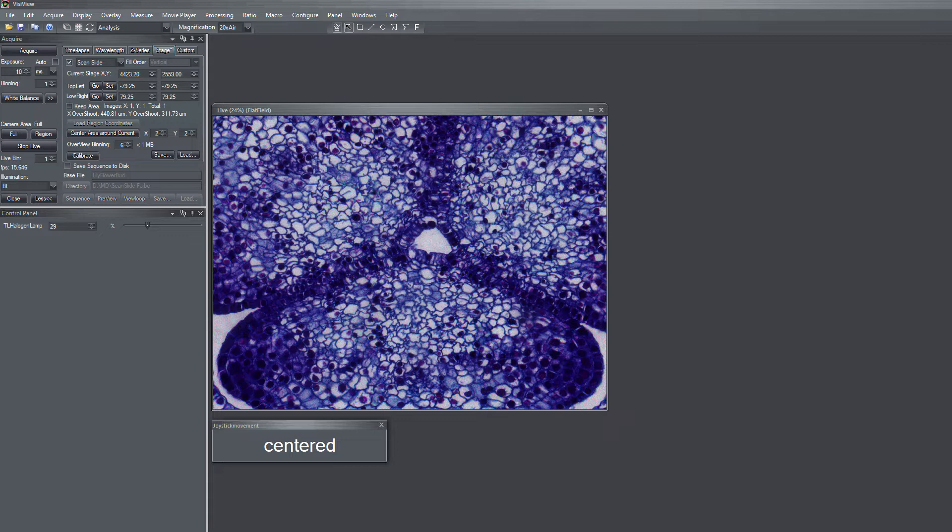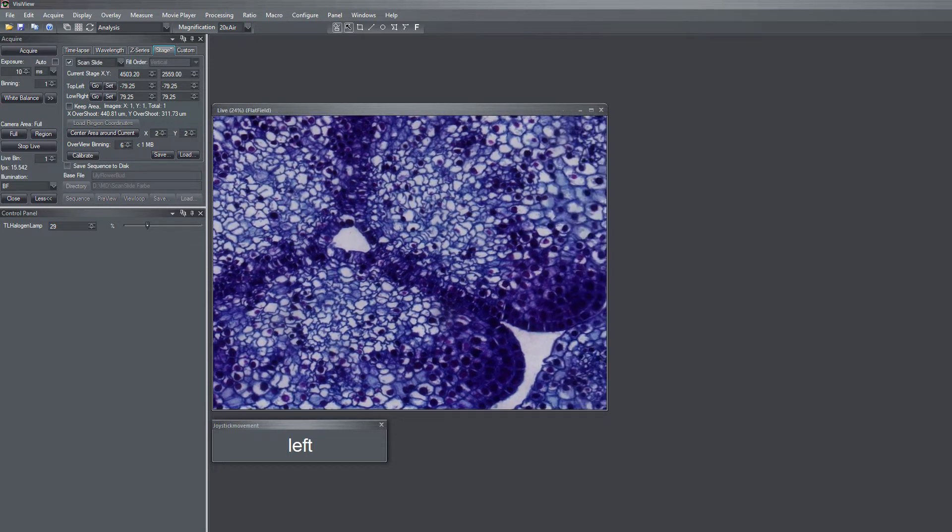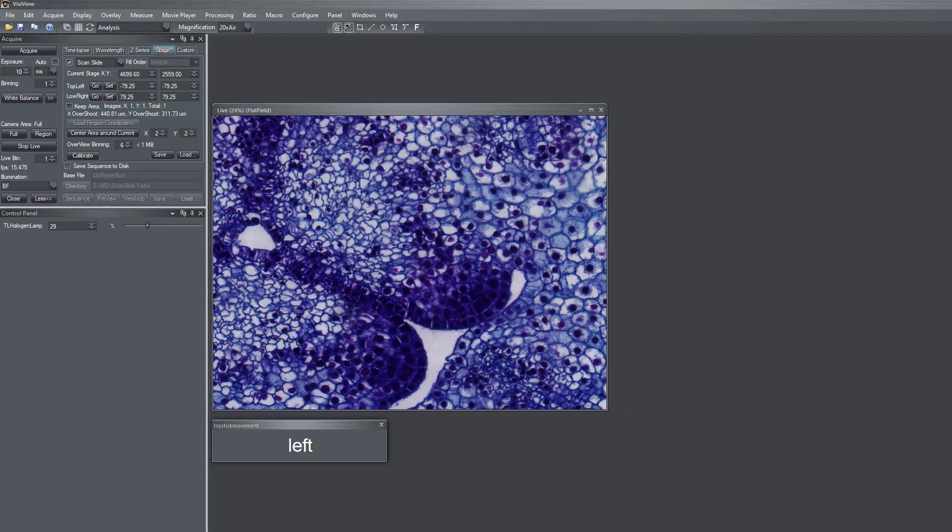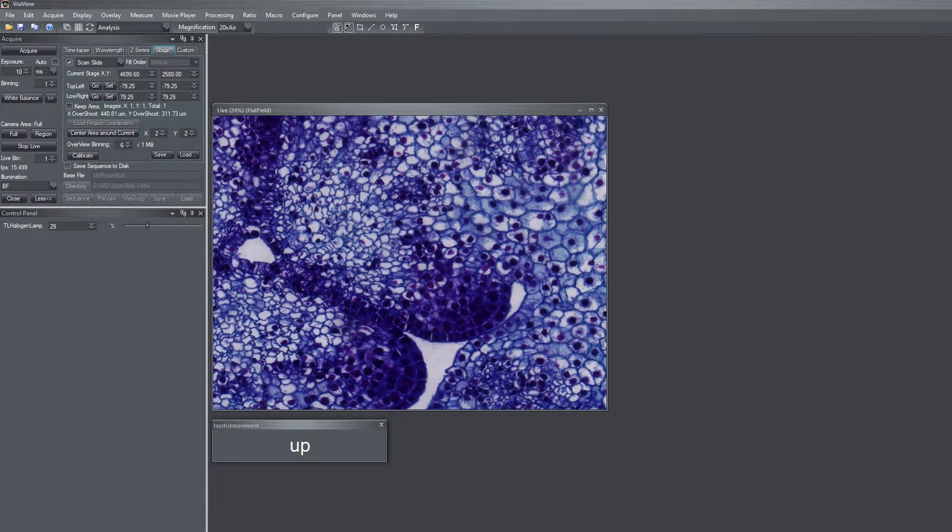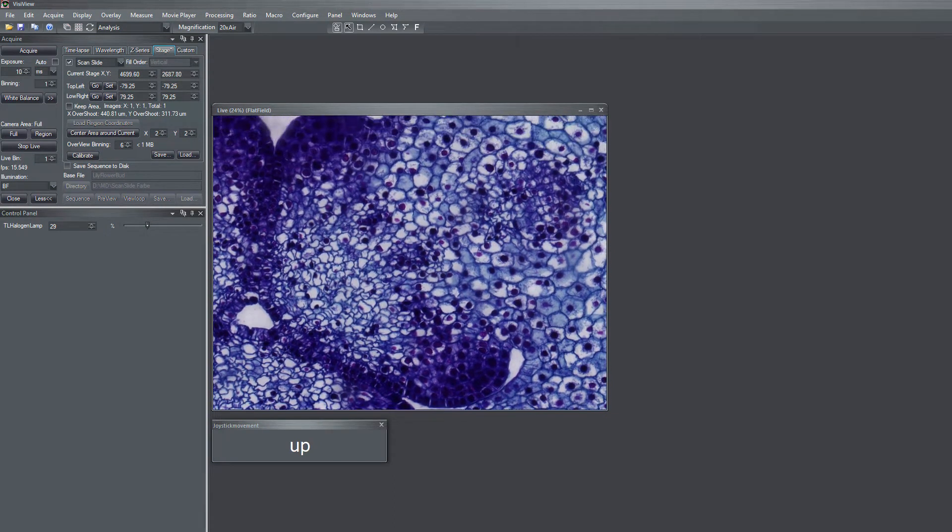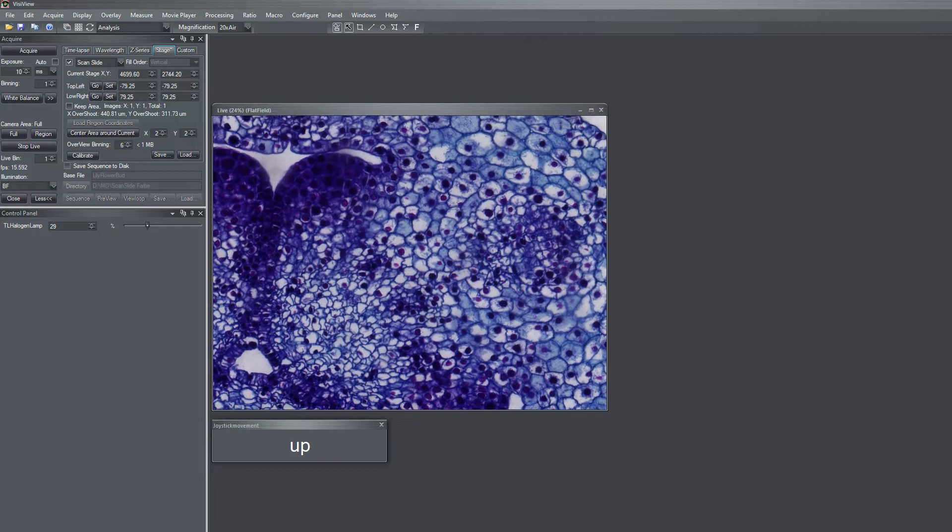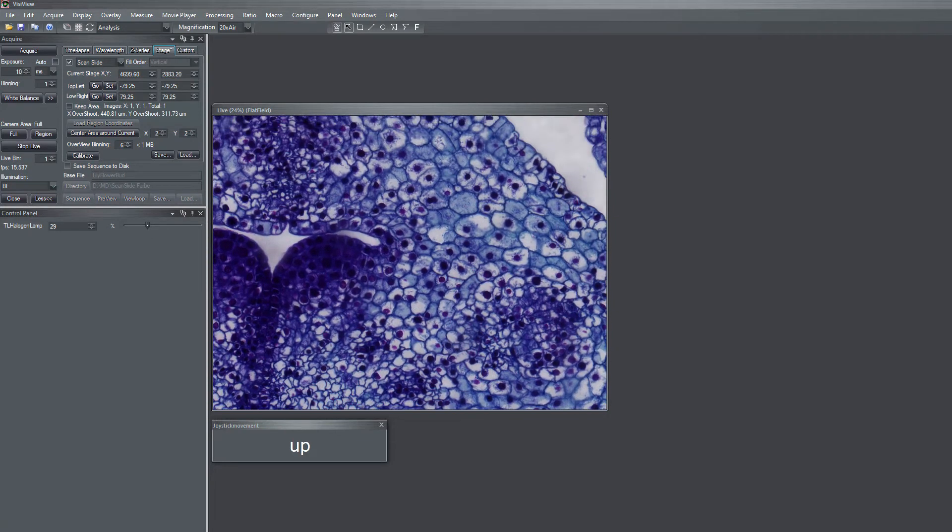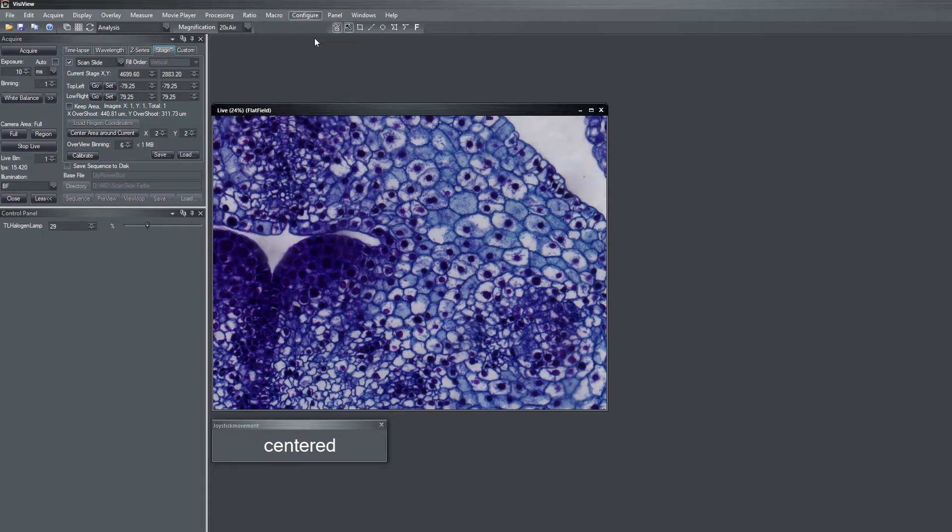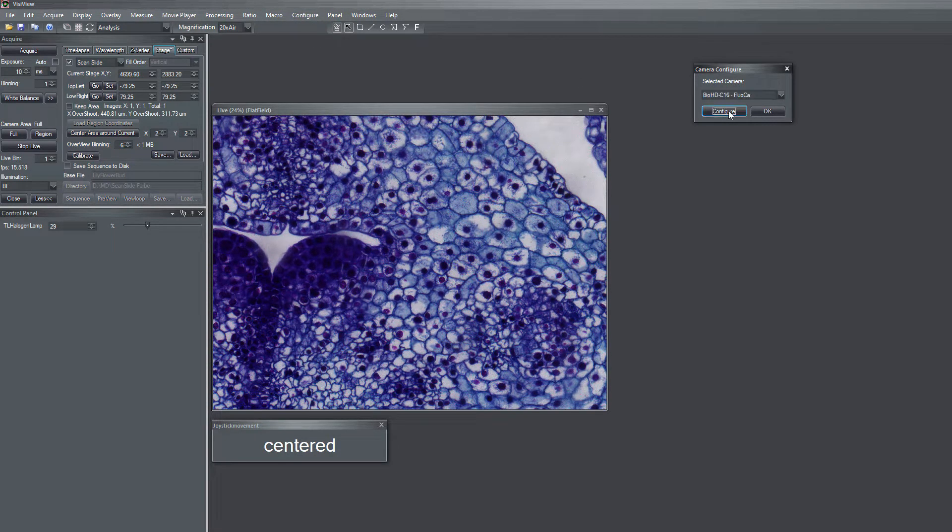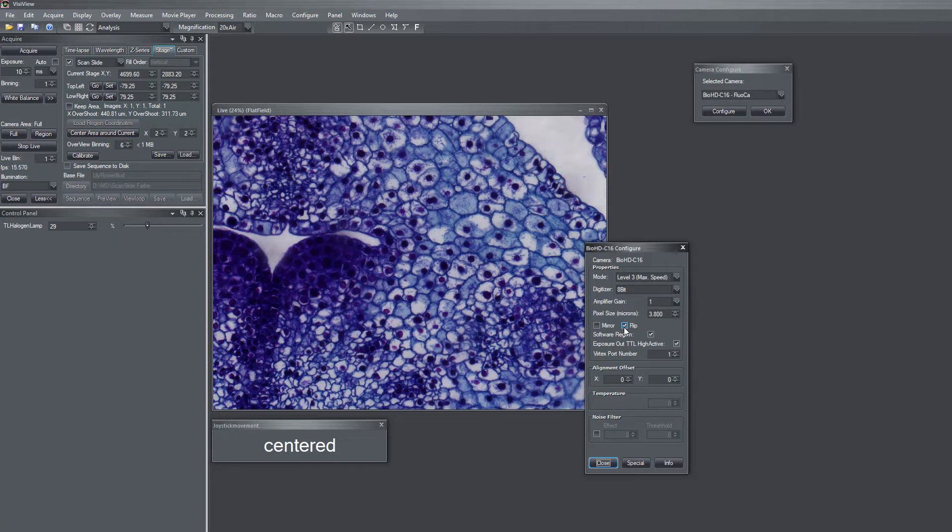If you move the stage to the left, then the sample moves also to the left. But if you move the stage up, the sample moves down. So there is a discrepancy between the x- and y-axis. And in order to fix this, you go to camera configure dialog and simply flip the y-axis which in this case behaves wrongly.